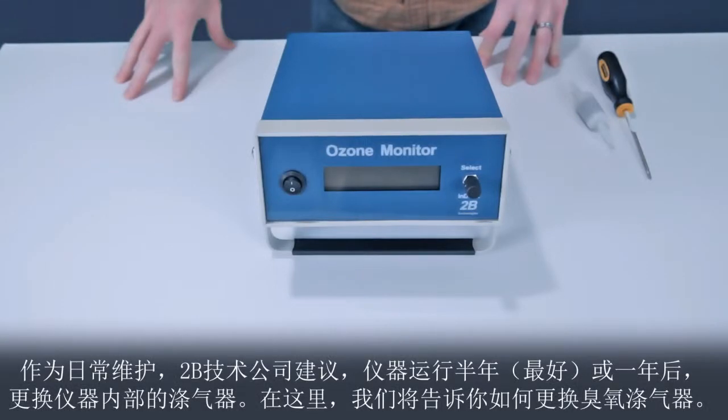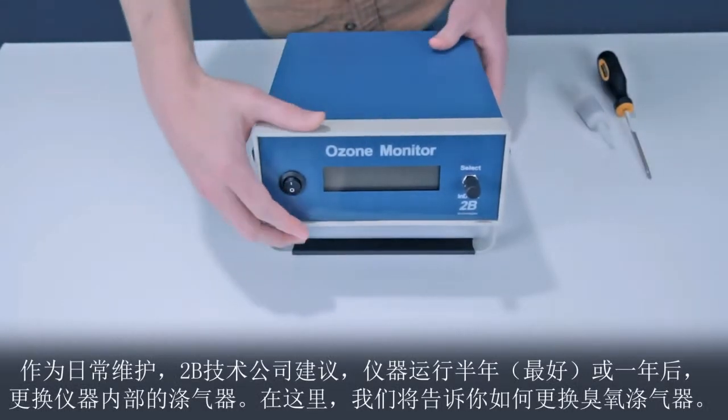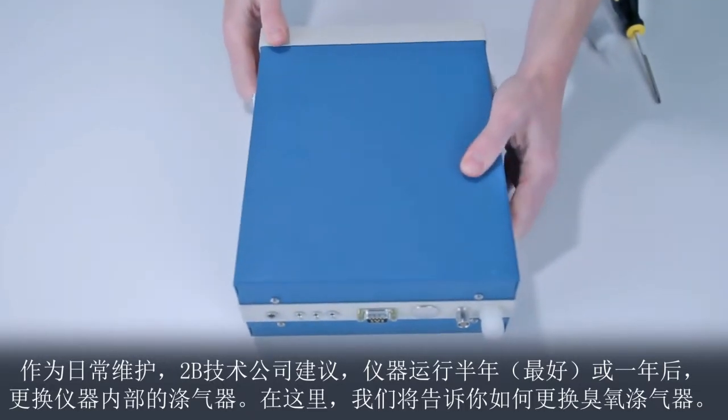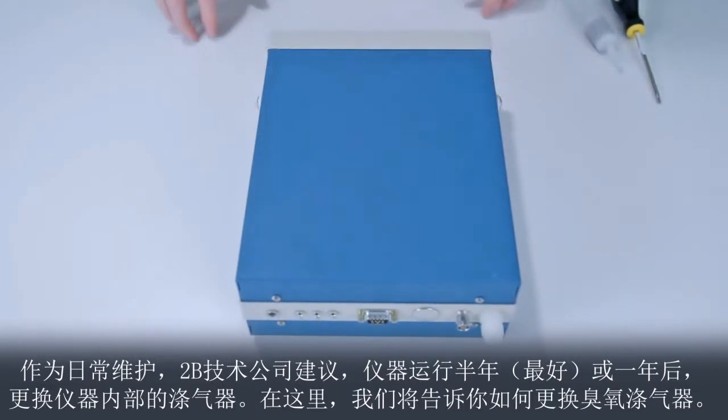As routine maintenance, 2B Technologies recommends that the internal scrubber be changed after one year of operation, and preferably every six months. Here we will show you how to change the ozone scrubber.